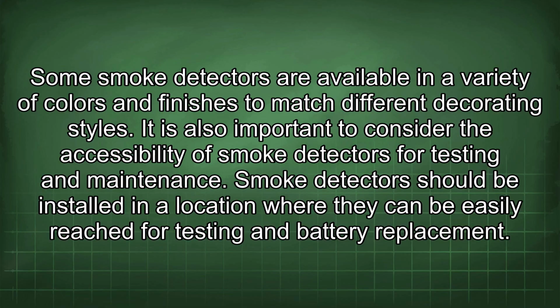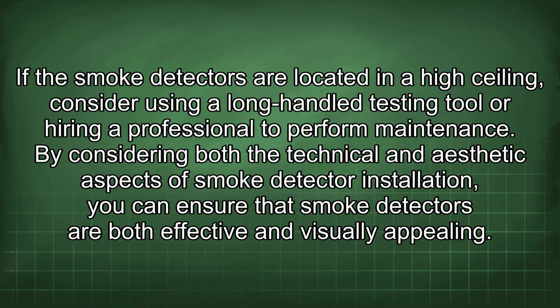It is also important to consider the accessibility of smoke detectors for testing and maintenance. Smoke detectors should be installed in a location where they can be easily reached for testing and battery replacement. If the smoke detectors are located in a high ceiling, consider using a long-handled testing tool or hiring a professional to perform maintenance. By considering both the technical and aesthetic aspects of smoke detector installation, you can ensure that smoke detectors are both effective and visually appealing.